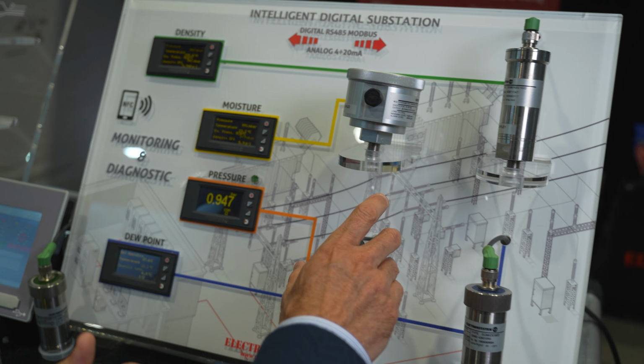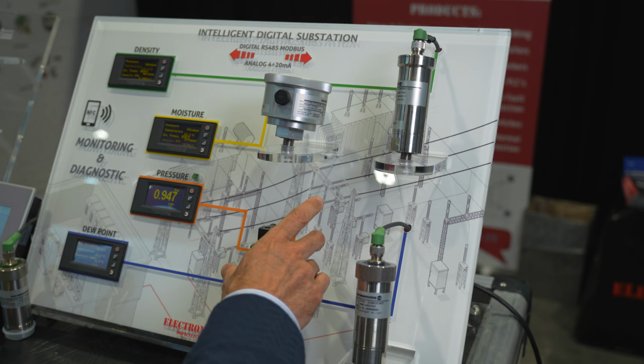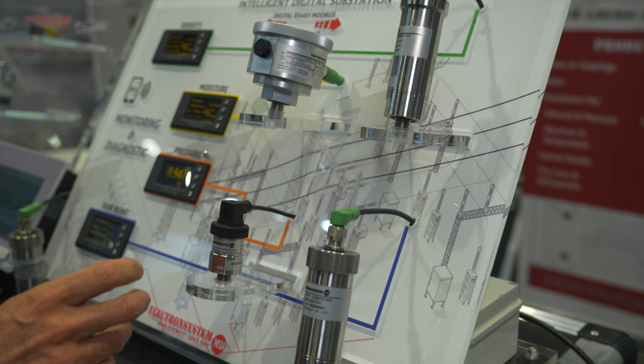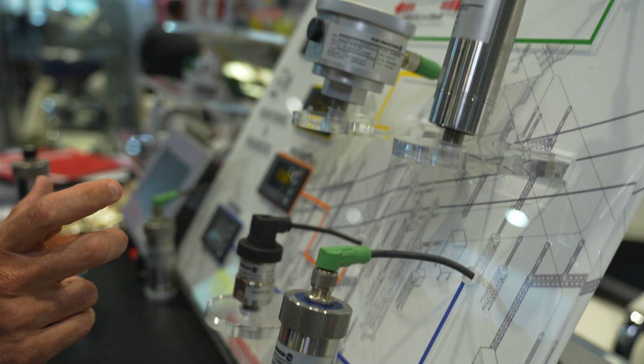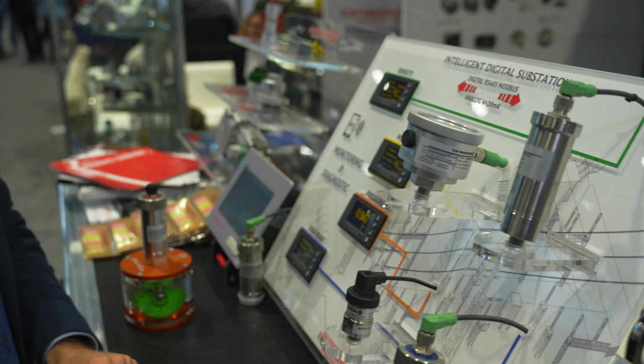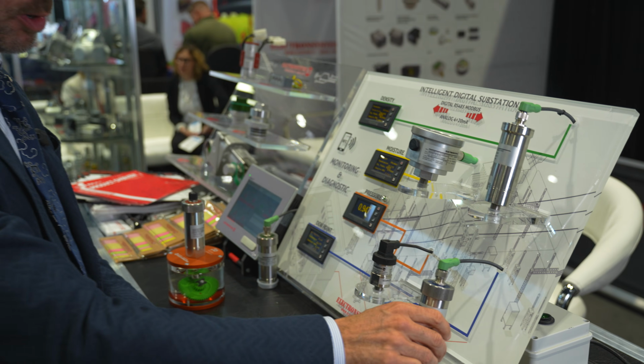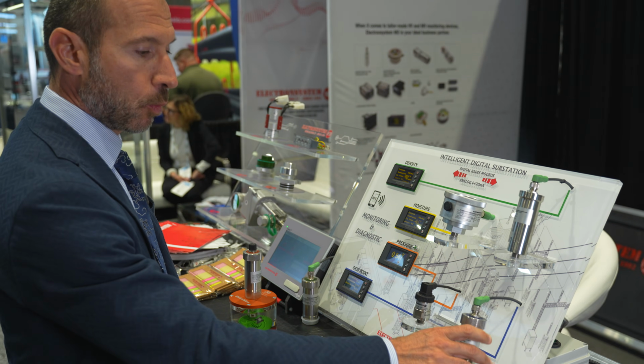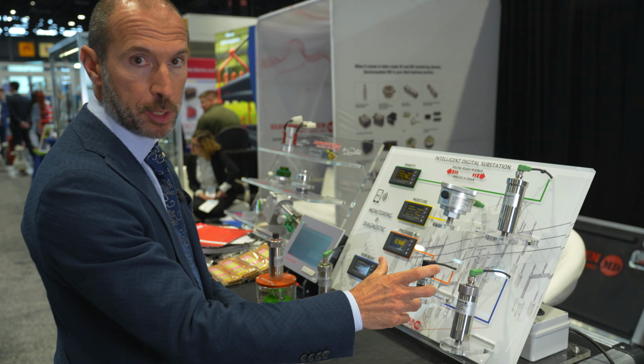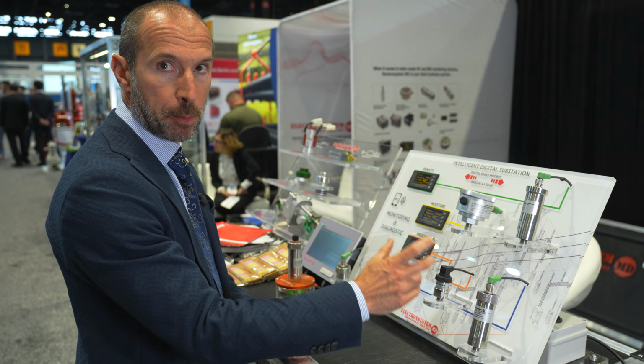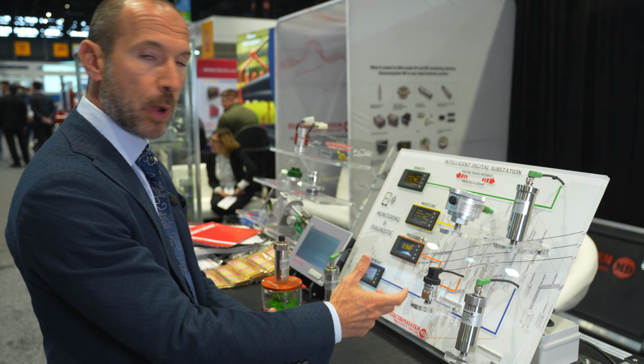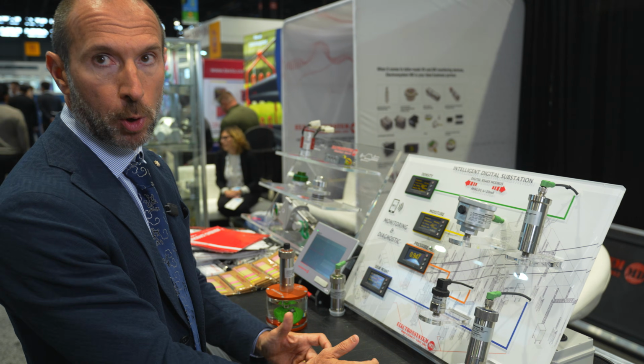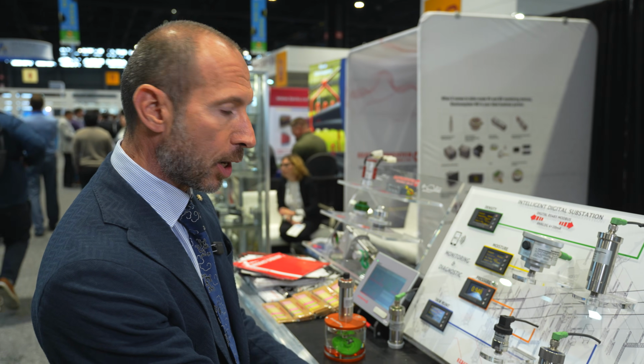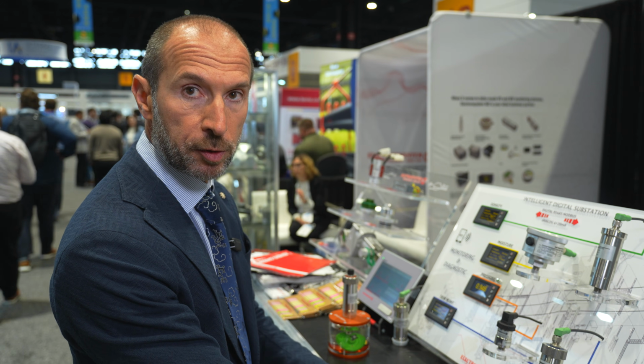We have simple pressure sensors in case we are working with a low pressure where the temperature is not varying so much. We have a specific sensor for moisture, where we can read the relative humidity, we can read the temperature, and we calculate by our sensors the dew point temperature, which is the temperature at which humidity condensates inside the gas.